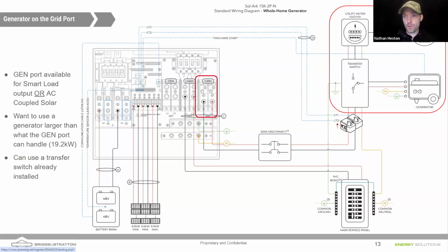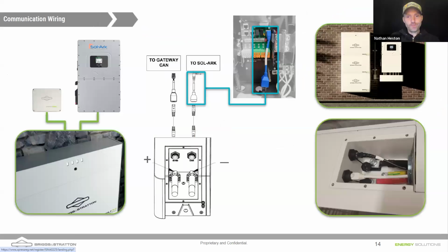That would be a very big generator, right? 24 kilowatts is 100 amps. So it would be 48 kilowatts of continuous power you could bring in from your generator. It also frees up the gen port to use it as a smart load port. Again, my favorite use of that gen port. So if you can put in a transfer switch, you can bring in that generator on the utility connection side, on the grid side.